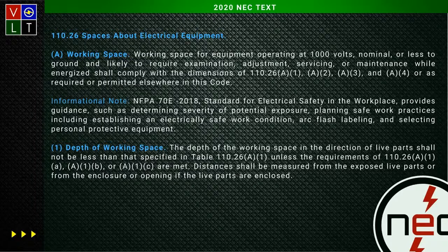When you're doing a hazard risk category and looking at the NFPA 70E document, it tells you certain specific equipment. Listen to what I'm saying: if that piece of equipment and that type of task is not listed, then that table does not apply at all, period. That's in the discussion. It does not apply. It's not a hazard risk category.